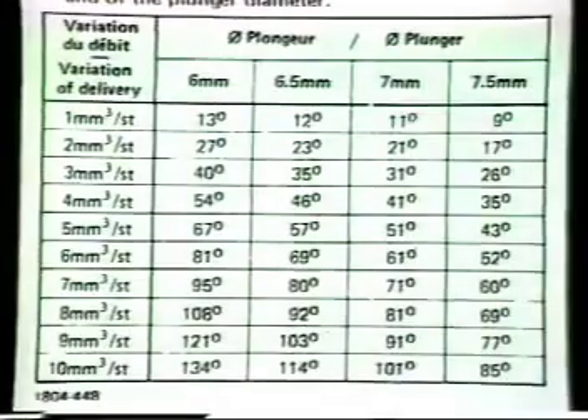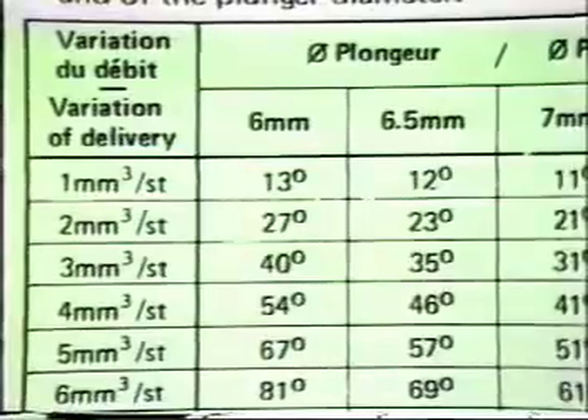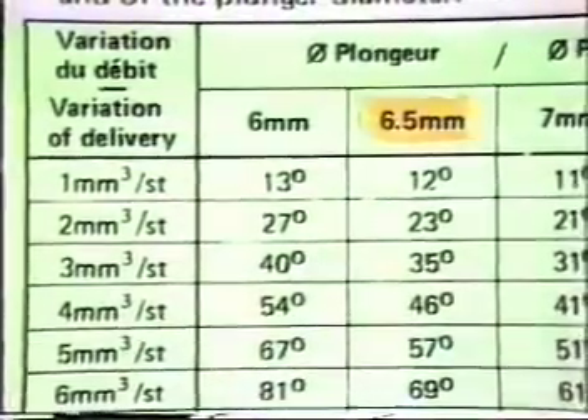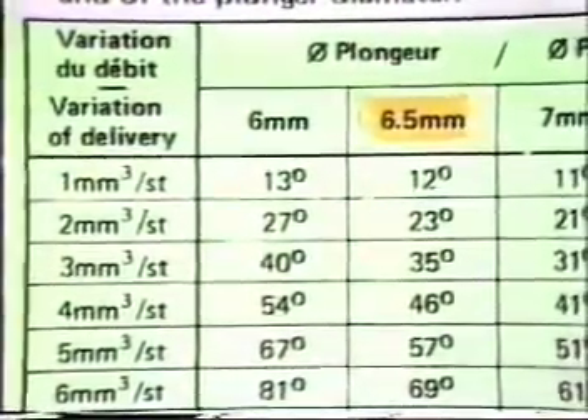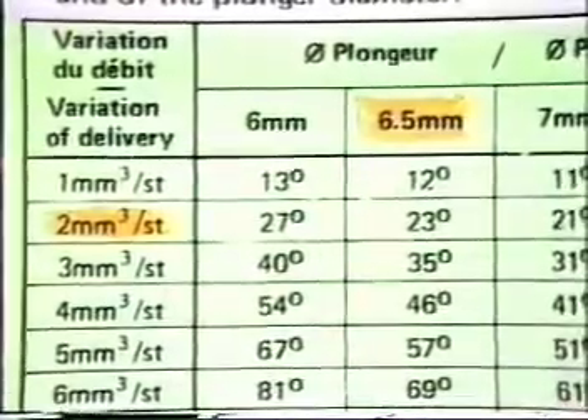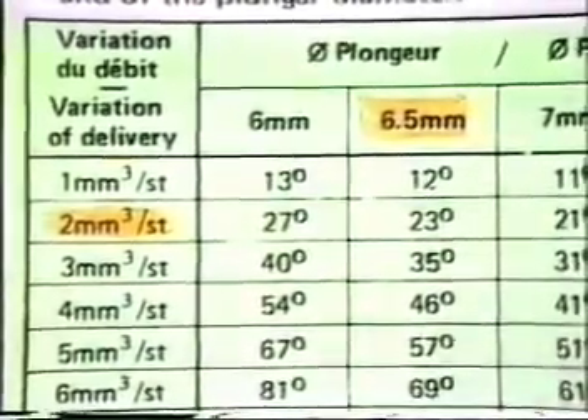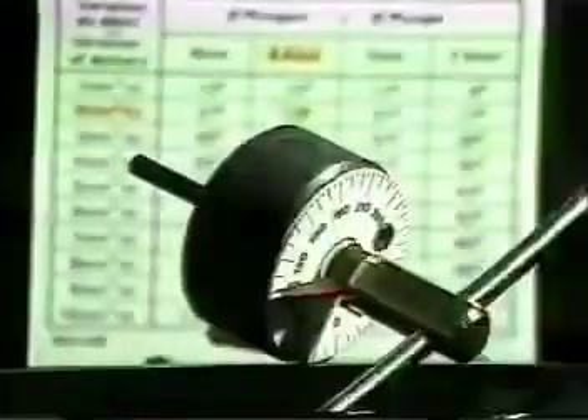In this example, the flow rate should be 33.7 plus or minus 0.5 cubic millimeters. As you can see, the flow rate is below the minimum, so it must be readjusted. Take the flow correction table and first position yourself at the piston diameter of 6.5 millimeters. In this case, the flow increase decided is 2 cubic millimeters, so the angular correction to give to the screw is 23 degrees.